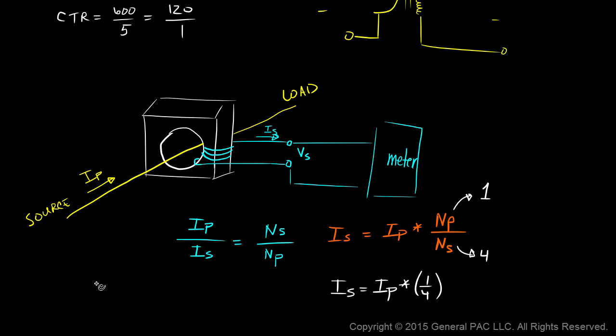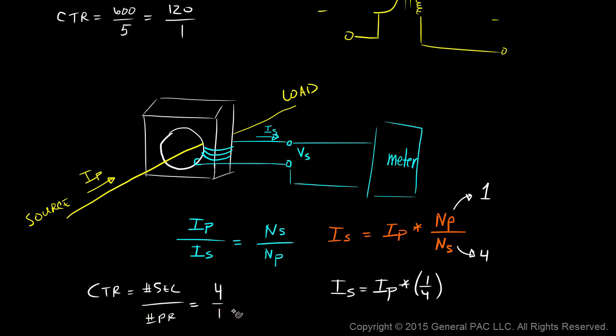Our CTR equals the number of secondary turns divided by the number of primary turns, which is 4 over 1. So in this particular example, our CTR is 4 — very simple.